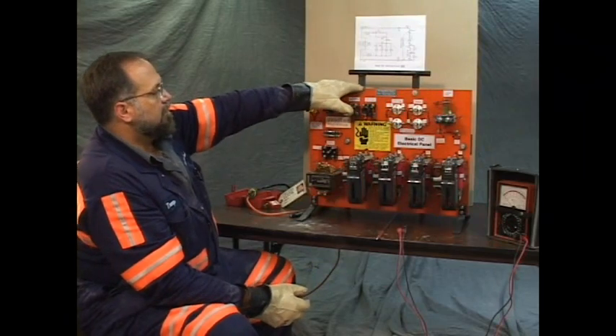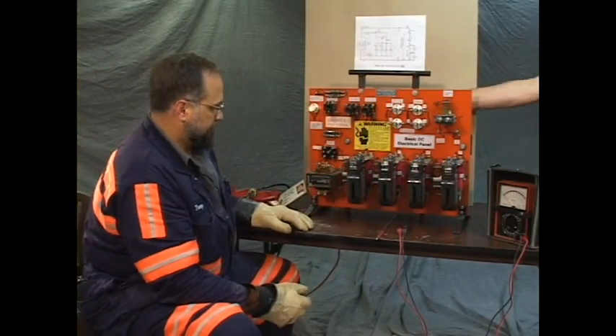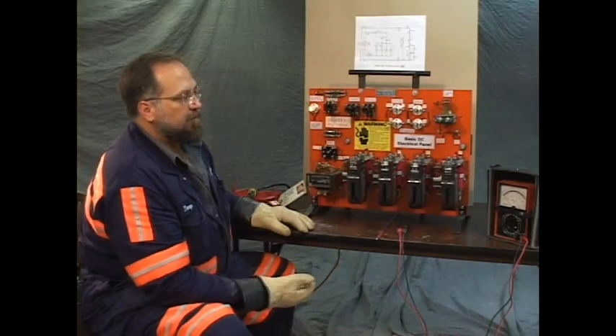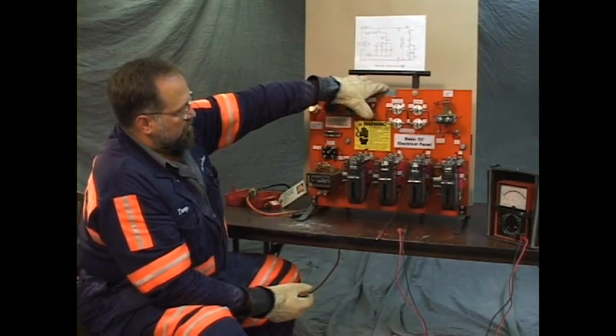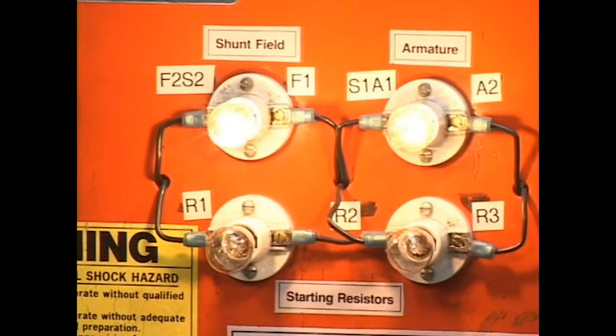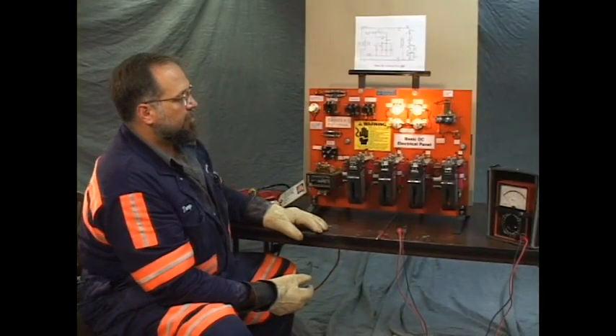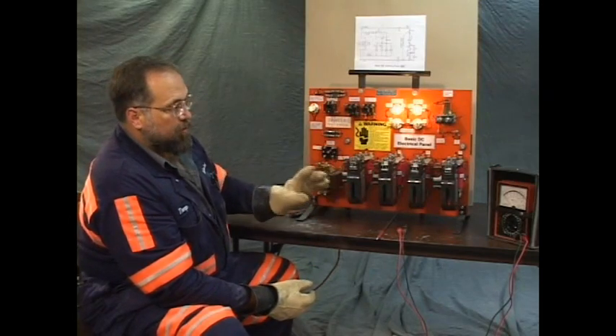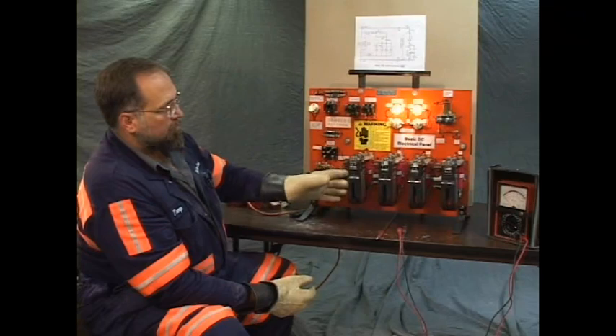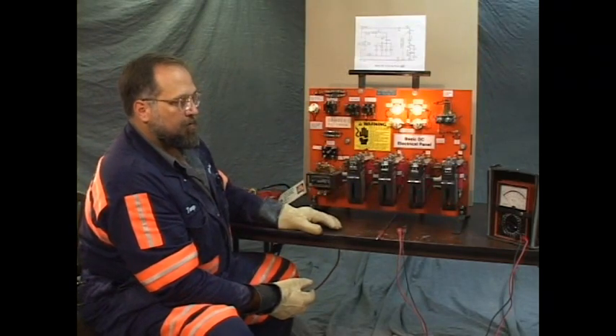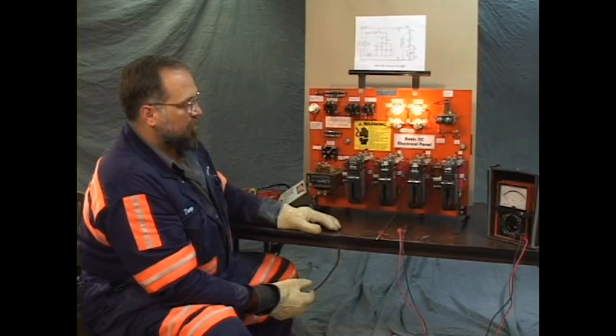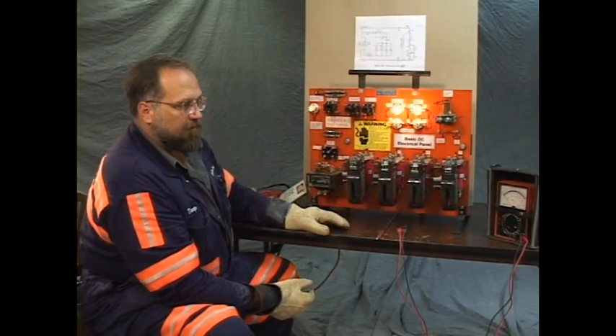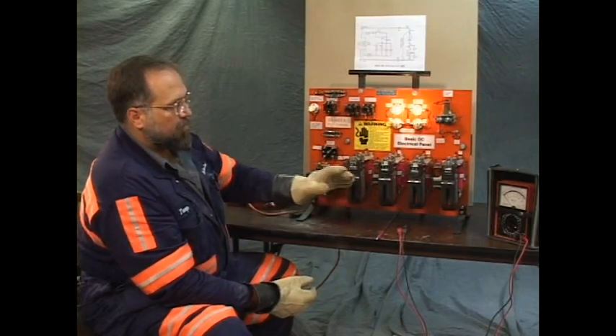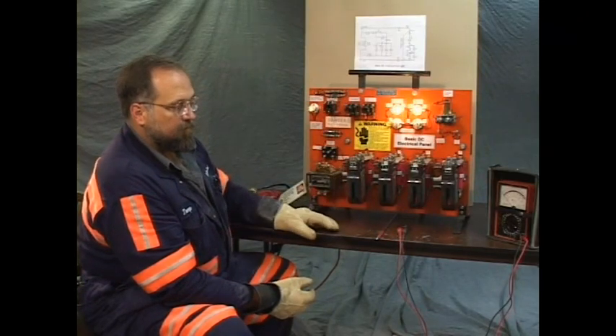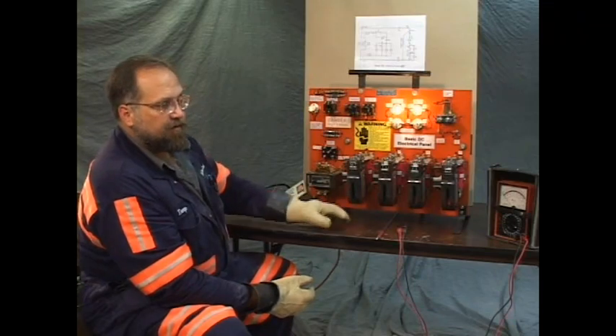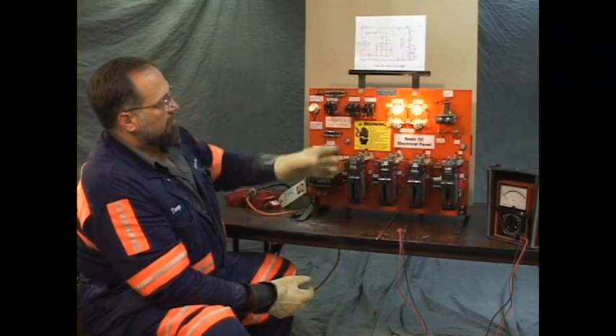Now we're going to toggle switch number 13. This is with the problem installed. This will be in malfunction. A couple of things you should have noticed right off the bat. I only had 2 clicks. All the contactors are in, so that would cause you to think that the timing is off. The timing sequence is off. We closed all the contactors, but we closed either 2 at a time twice or 3 at a time and then 1 by itself.